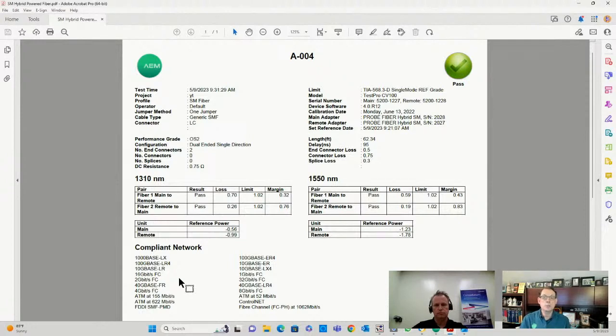So in this case, if you installed, say, 8 strands of fiber or 16 strands of fiber with 8 pairs of copper that go with it, you could test every 2 fibers and a pair of copper each time. You'd do your typical 2-fiber test throughout, and get the DC resistance information for that copper conductor.